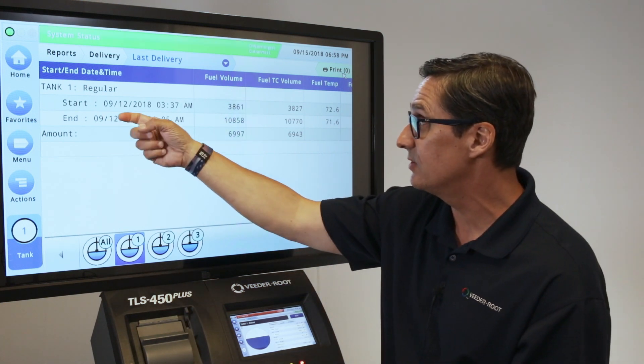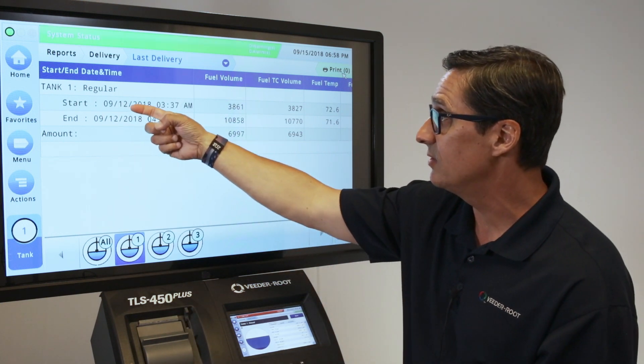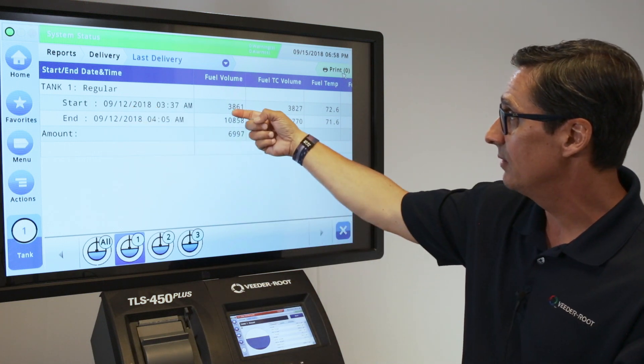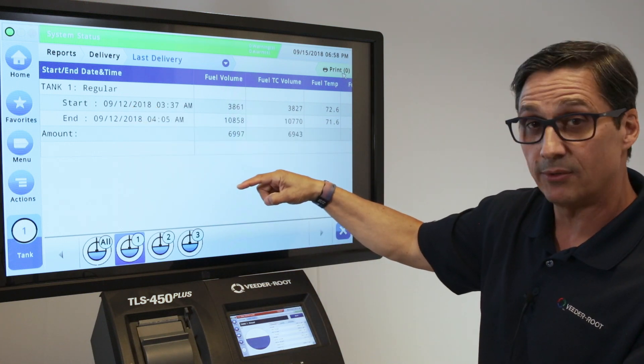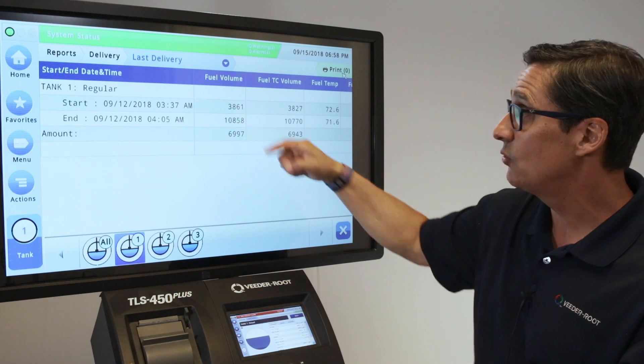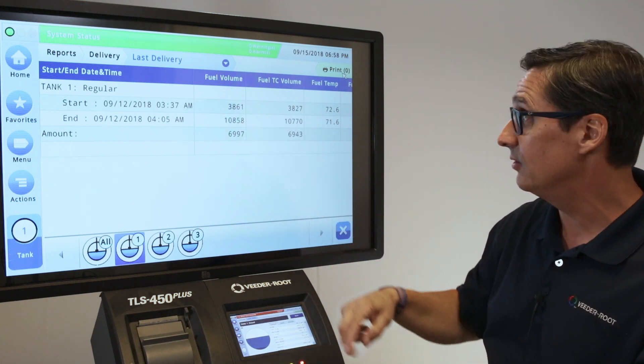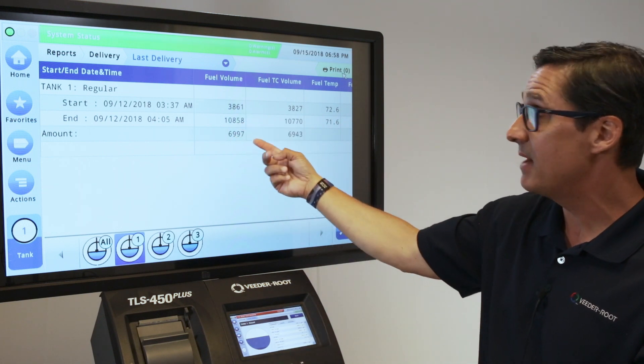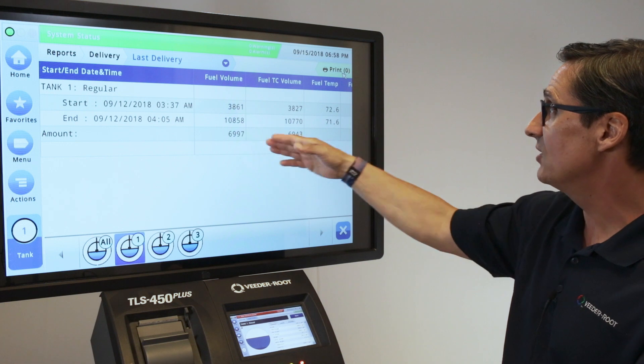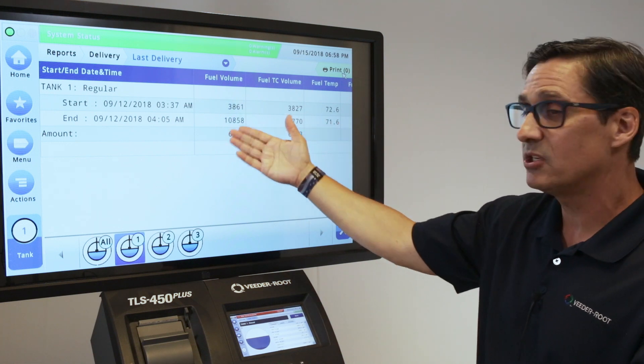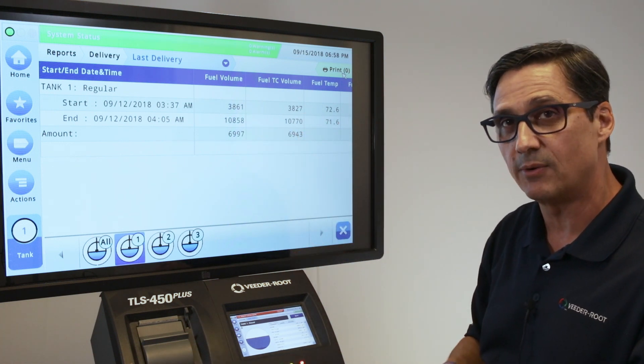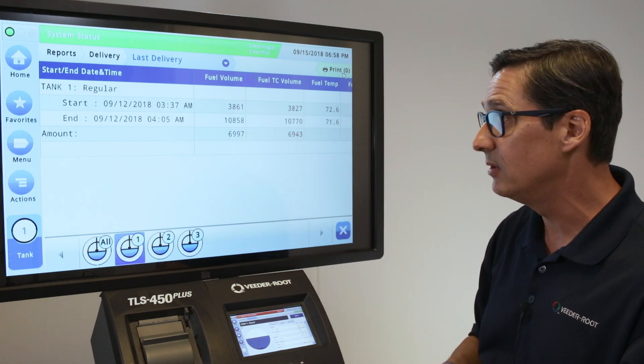This particular report is showing us a start date and end date, the fuel volume at the beginning of the delivery, what the inventory was at the end of delivery, and what the amount change was during that delivery. This is really important because you want to reconcile that with your ticket delivery information you're getting from the driver.